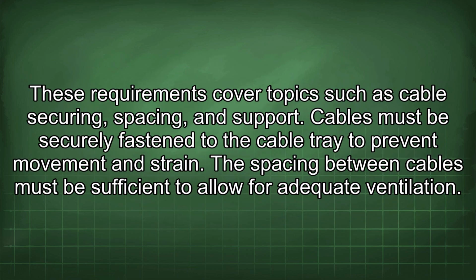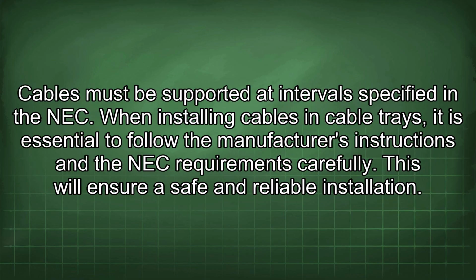These requirements cover topics such as cable securing, spacing, and support. Cables must be securely fastened to the cable tray to prevent movement and strain. The spacing between cables must be sufficient to allow for adequate ventilation. Cables must be supported at intervals specified in the NEC. When installing cables in cable trays, it is essential to follow the manufacturer's instructions and the NEC requirements carefully. This will ensure a safe and reliable installation.